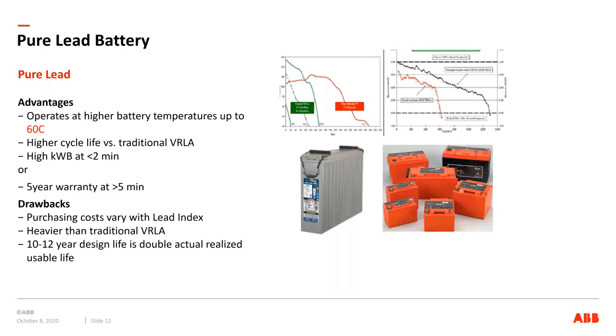It addresses some of the issues with the traditional VRLA battery. They are typically more robust temperature-wise. There are actually special versions that can operate all the way up to 60 degrees, of course, with shorter life. But generally, they can handle more of a temperature swing than a traditional VRLA, and they have a better performance.